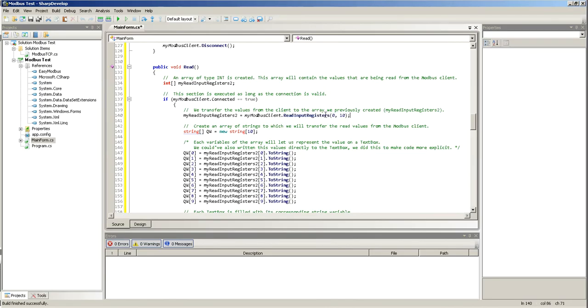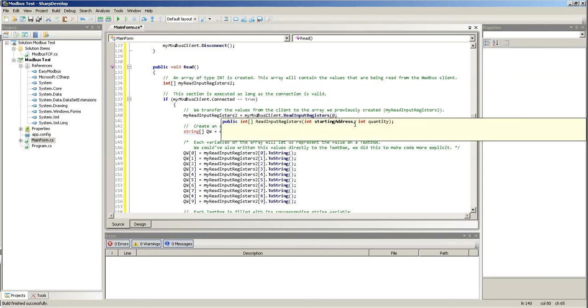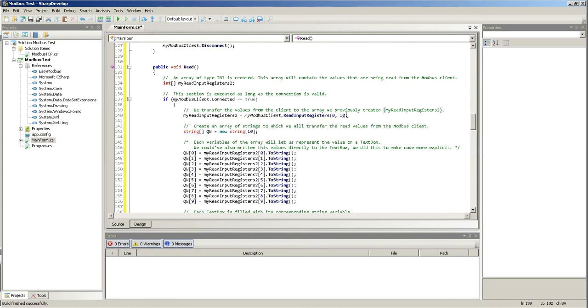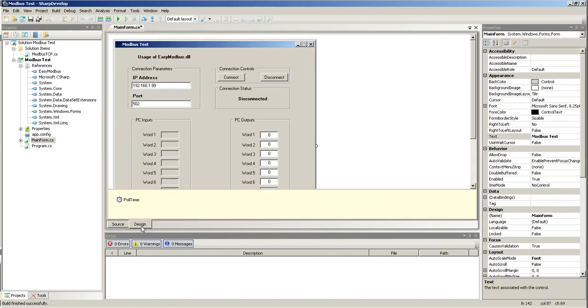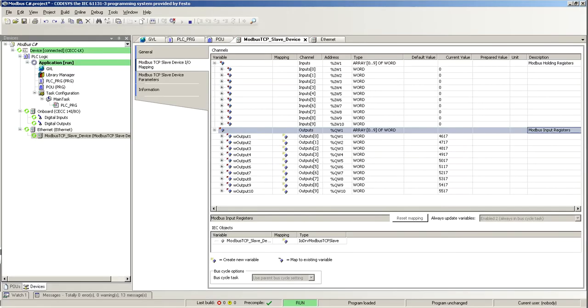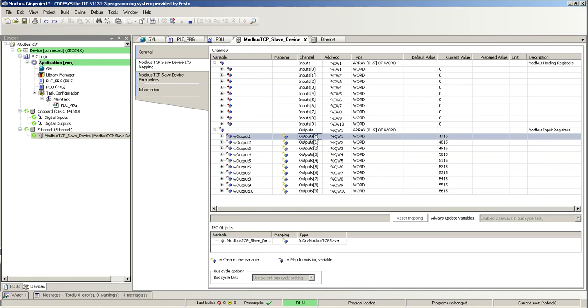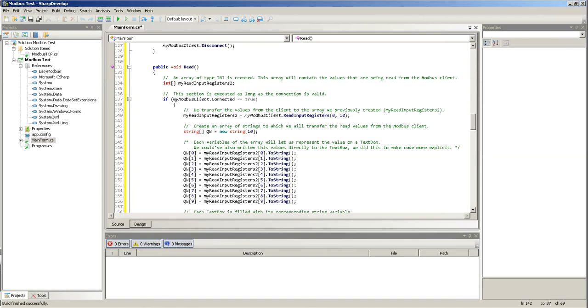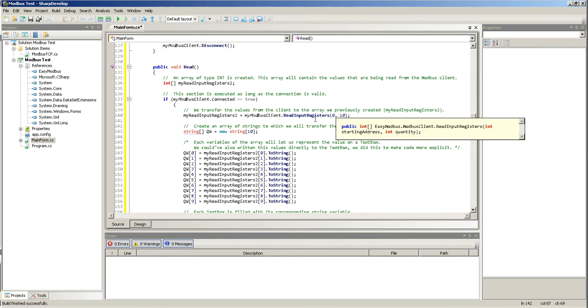So, read input registers, and now zero, zero means the starting address, and I can look at that if I just hit here. So, it's an integer, starting address, and then the quantity, 10. And how did I come up with those numbers? So, if I go here, I'm starting from, so this will be my zero, and this will be 10. If I had more outputs, like 15, then I will put 15, or depending on which ones I want to read. And then, the 10, of course, is the amount that I want to read.